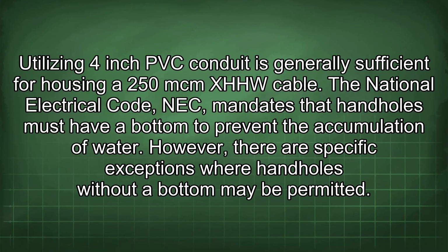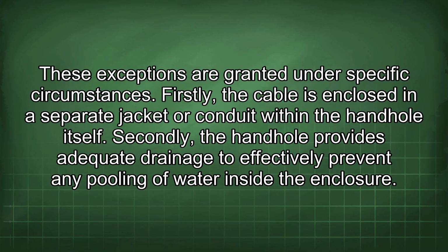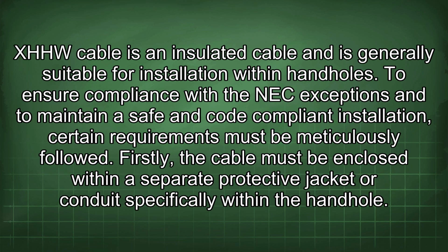The National Electrical Code (NEC) mandates that handholes must have a bottom to prevent the accumulation of water. However, there are specific exceptions where handholes without a bottom may be permitted. These exceptions are granted under specific circumstances. Firstly, the cable is enclosed in a separate jacket or conduit within the handhole itself. Secondly, the handhole provides adequate drainage to effectively prevent any pooling of water inside the enclosure. XHHW cable is an insulated cable and is generally suitable for installation within handholes.